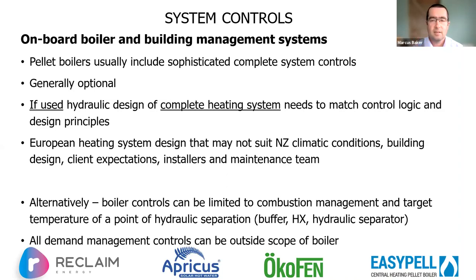If we start mixing and matching, using a kind of New Zealand approach to our hydraulic design and then expecting the boiler to provide the control system, you're almost certainly going to have minor to very major headaches over commissioning and system operation, because European heating system designs are often quite different and might not suit our conditions and our expectations and our designs and maintenance.